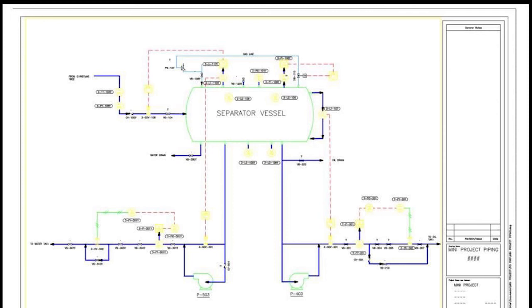The level transmitter from the vessel is connected to the shutdown valve through an emergency shutdown with an electrical signal. After the transducer, a pneumatic line is drawn, reconnecting it back to the flow check valve, completing the flow control loop for the water pipeline.